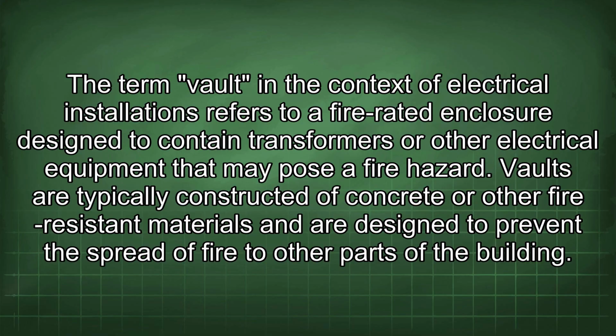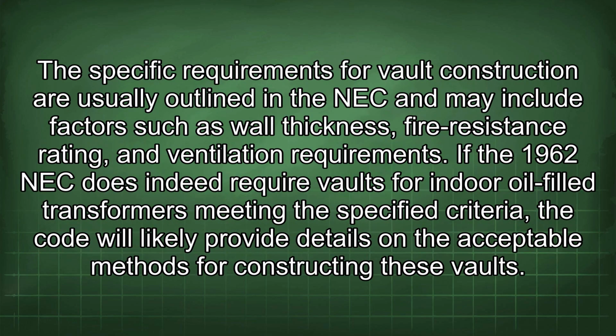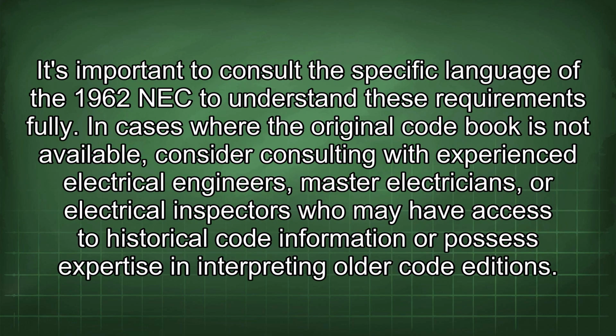Vaults are typically constructed of concrete or other fire-resistant materials and are designed to prevent the spread of fire to other parts of the building. The specific requirements for vault construction are usually outlined in the NEC and may include factors such as wall thickness, fire resistance rating, and ventilation requirements. If the 1962 NEC does indeed require vaults for indoor oil-filled transformers meeting the specified criteria, the code will likely provide details on the acceptable methods for constructing these vaults. It's important to consult the specific language of the 1962 NEC to understand these requirements fully.